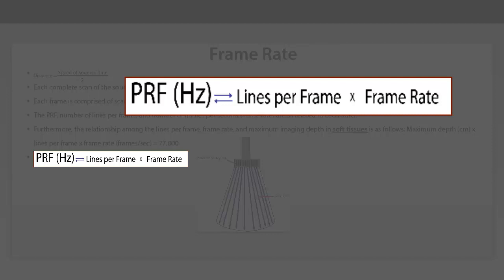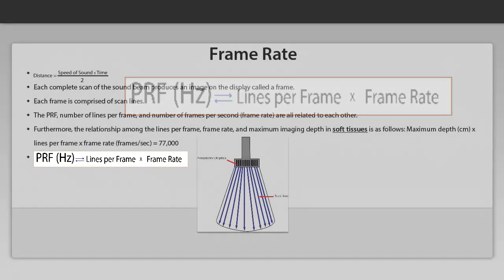Also, in order to increase the number of lines per frame, you need to increase the pulse repetition frequency and vice versa.